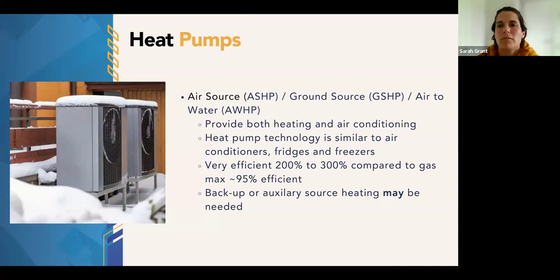And so if you don't have an HVAC permit, it's sometimes smoother. But if you have an HVAC permit, sometimes these bylaw officers may get a little bit fiddly and want you to have the electric auxiliary source, which can be fought. But when it comes to sizing heat pumps, sometimes you don't necessarily want to size your heat pump to do 100% of your heating requirement anyway. It's often a bit better for the heat pump and more efficient to size it slightly lower so that it might do most of it up until say -10 or -15, and then you have this smaller auxiliary for when it gets really cold. But there's nothing in the bylaw that requires the backup.